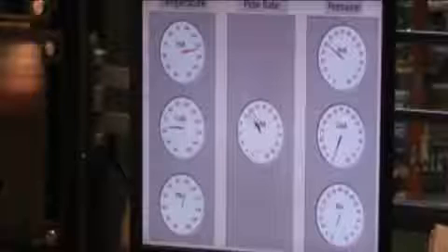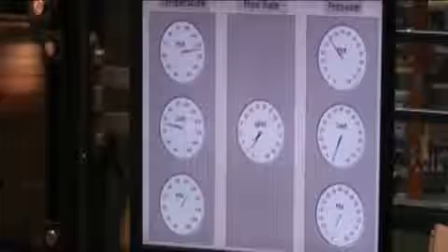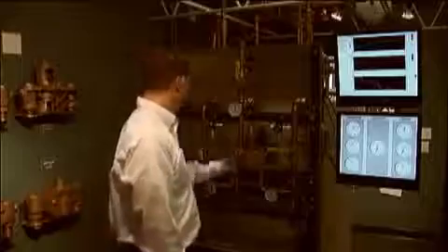The thermostat will expand and shut down the flow of water. As you can see, we've shut off the flow of water on our instrumentation here, and now we're just emptying out what's left over in the pipe. Once I allow the hot and cold water to flow back through the valve equally, we'll quickly return to our desired set temperature.